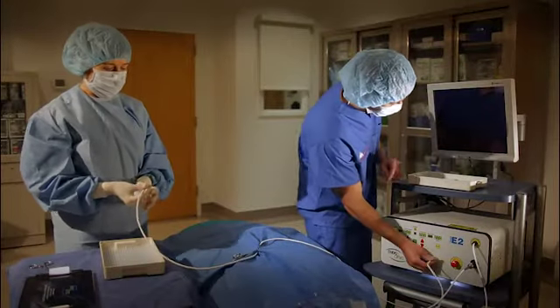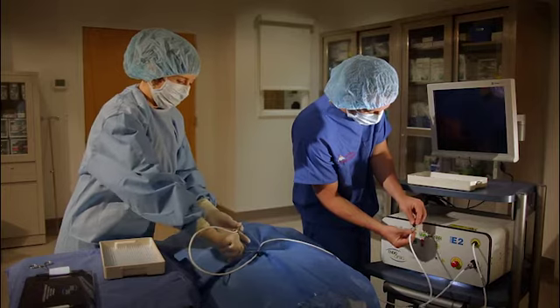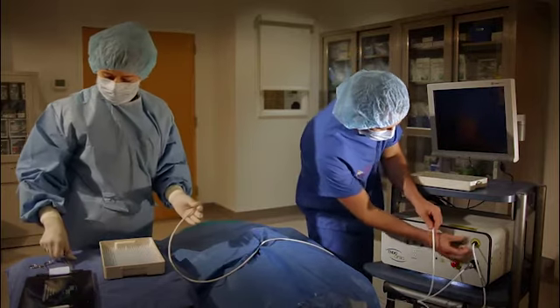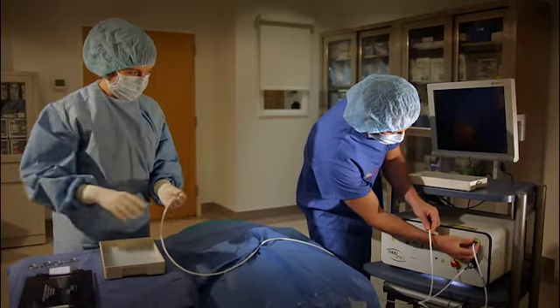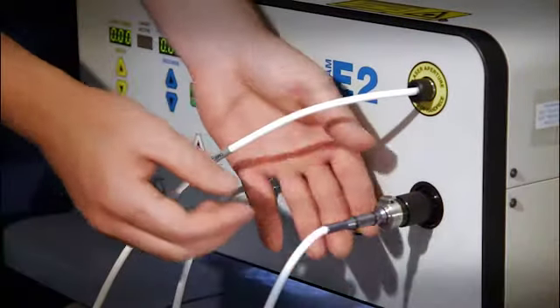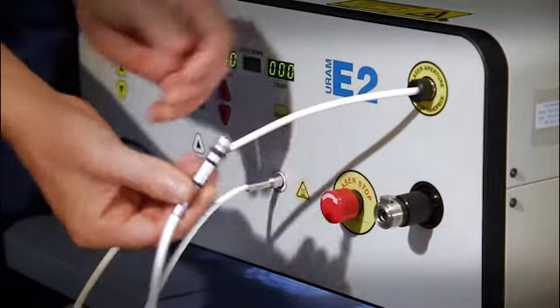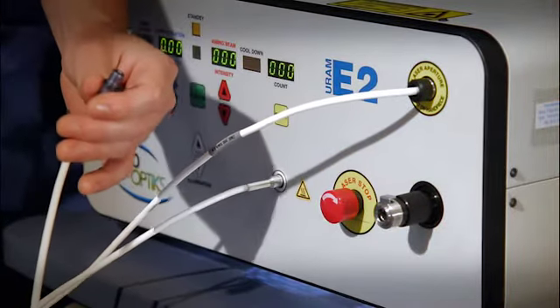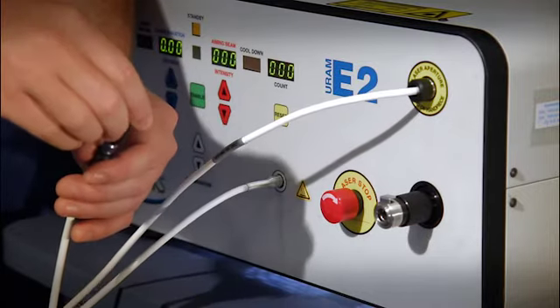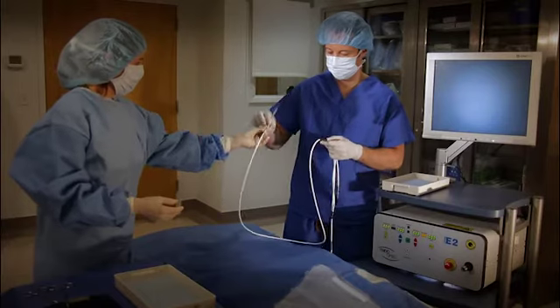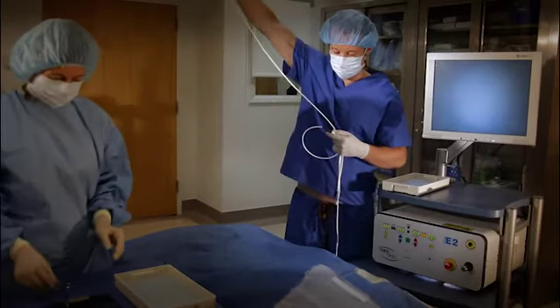The 3 connections to the unit are then disconnected, being careful to remove them by holding the connector ends and not by pulling on the white sheathing. Use the release lever to detach the video connector. Protect the ends by replacing all connector caps. Extra caps are included with each endoscope. The circulating nurse then accepts the endoscope as it is passed from the sterile field.